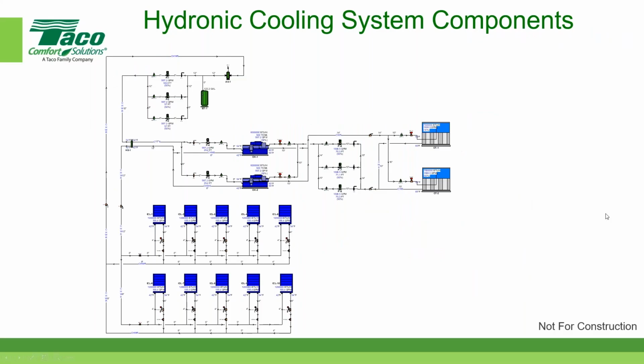Oh yeah. Here's a great question: why is the chiller inefficiency that needs to be rejected? But wait, I may be reading this wrong. Well, I'm going to read it like it says, and then maybe we can correct it, Robert. Why is the chiller inefficiency that needs to be rejected by the cooling tower so high? Seems like a huge inefficiency going from 2.4 GPM per ton to 3 GPM per ton.